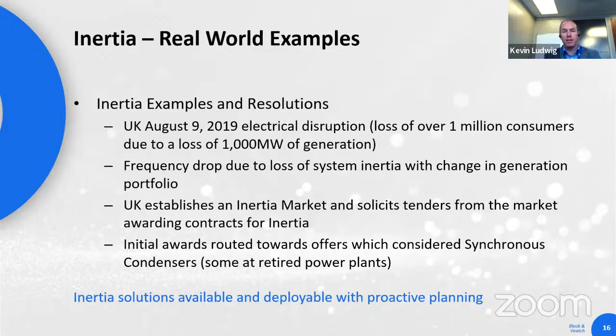What happened in the United Kingdom on August 9th, 2019 was a lightning strike on some transmission lines. That lightning strike caused the loss of a major link, which caused the loss of 1,000 megawatts of generation. One of the links affected was for an offshore wind project, and another for a conventional generation project. The UK electrical system had enough power on reserve to meet that loss of generation, but it didn't have enough inertia to maintain the 50 hertz frequency at the level it needed to be.